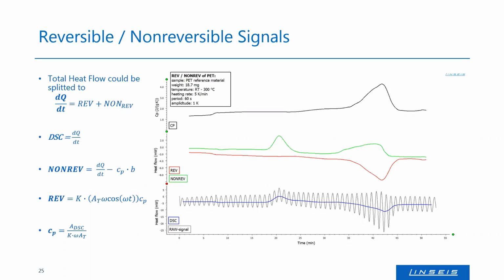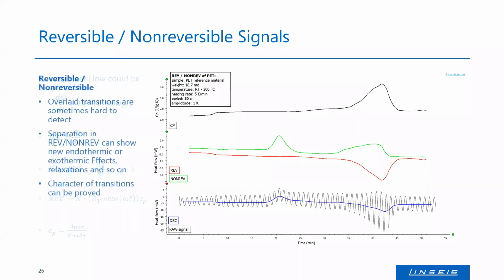So basically, the CP is defined as the amplitude of my DSC signal, which you can see here in the gray measurement, divided by the calibration factor multiplied with my period, so omega, multiplied with the amplitude of my temperature. This is how we receive the values for the CP and also for the reversing and non-reversing heat flow. Yep, I think I already discussed it with you a slide ago.